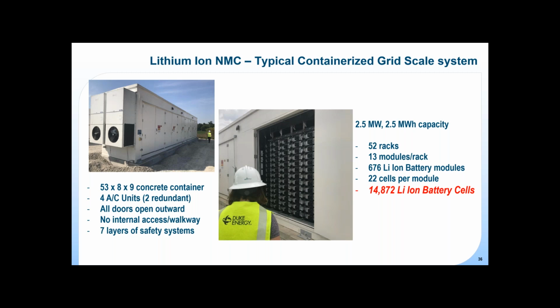Our typical building block approach has been a 2.5 megawatt hour capacity container using Samsung SDI modules to date. We've got 52 racks, 13 modules per rack, 676 lithium-ion battery modules in a container, at 22 cells per module, for a total of 14,872 lithium-ion battery cells in a container.